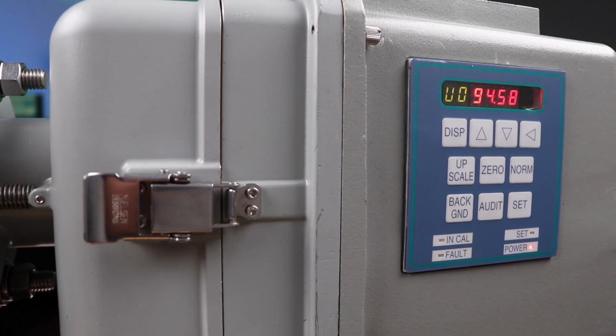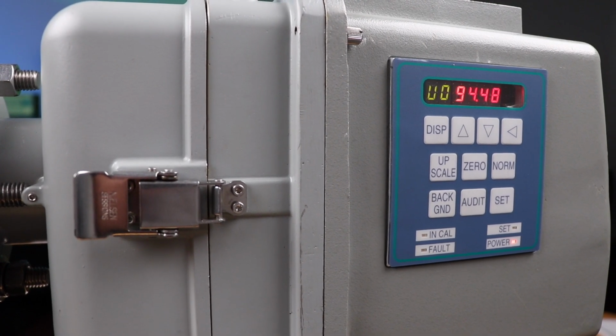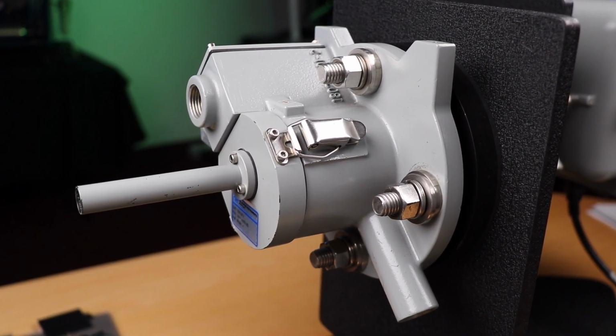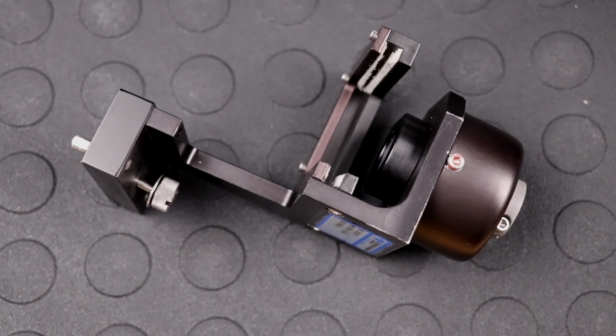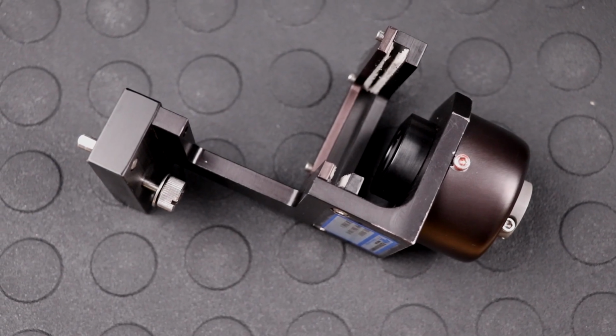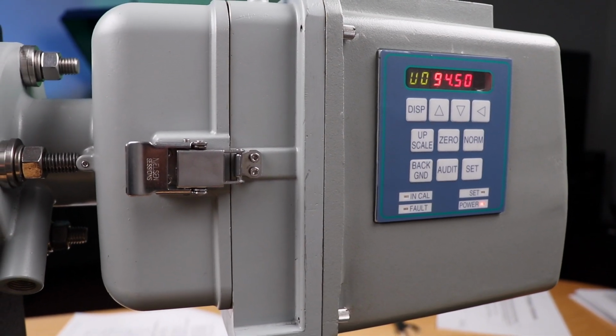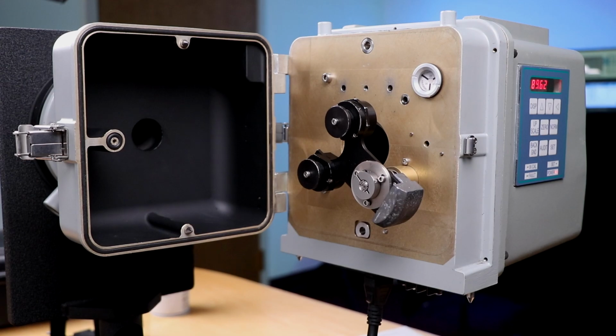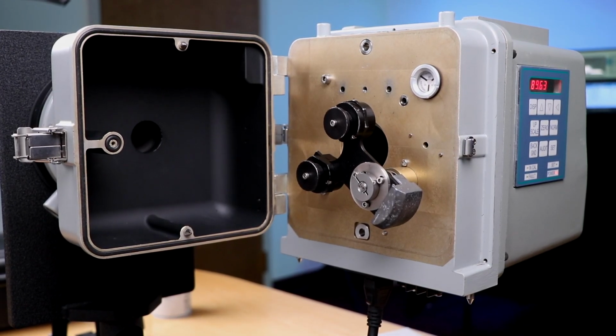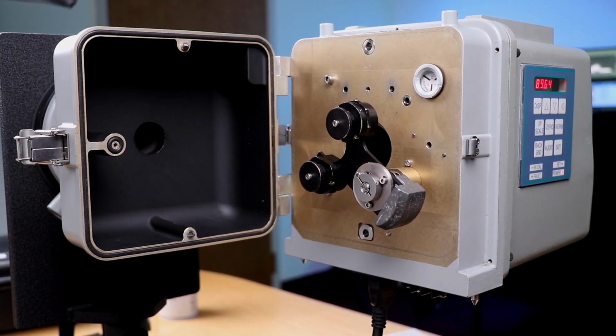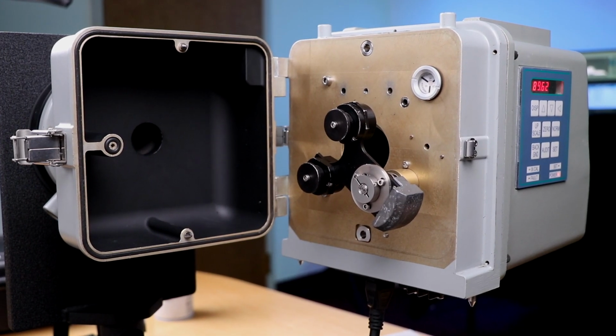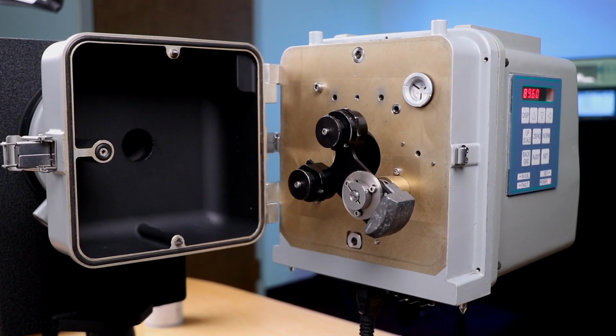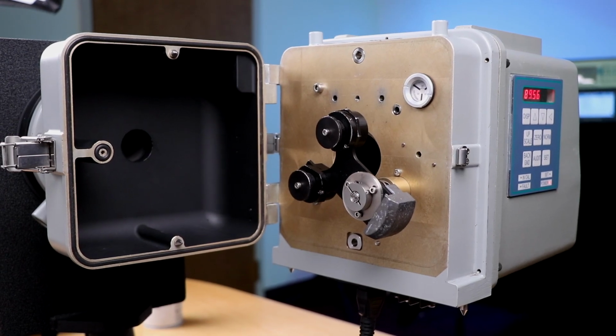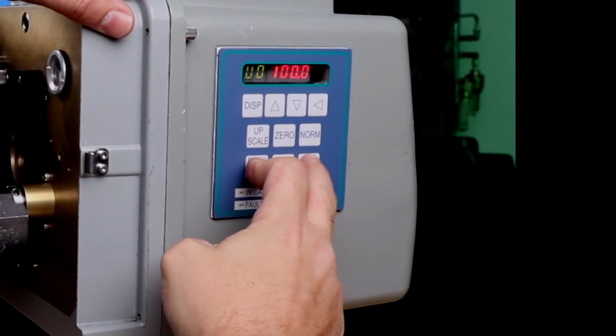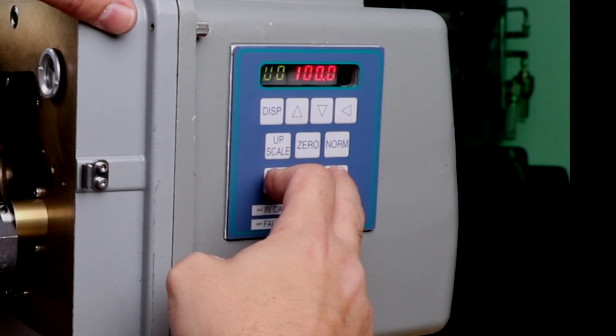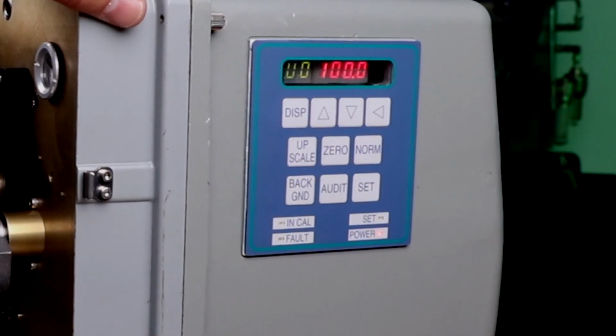The major components include the optical head, the retroreflector, and the calibration kit or audit device. The optical head contains all the electronics necessary to focus and project the light beam across the sample path, receive the light reflected back into the detector, determine the light attenuation, and deliver an opacity reading. The head unit is also equipped with a numeric keypad for operator interface.